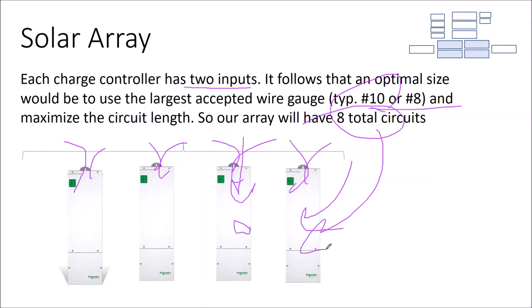And so what I did, because this is a pretty good design practice, for my cable sizing, rather than do a voltage drop calculation or an amperage calculation, all of which you need to do, you're going to want to upsize your cable, because the thicker your cable gauge, the more efficient the system is. In off-grid, even in grid connection, it's worth it to spend money on efficiency. So I started with the terminal block that the solar circuits land on with a charge controller. That told me we need two inputs, two circuits, and that means we're going to have 8 circuits on the rooftop. And then what's the cable size going to be? Well, the largest cable that they accepted was number 10. So we went with number 10 cable going into our circuits, and that just set the design from that point.